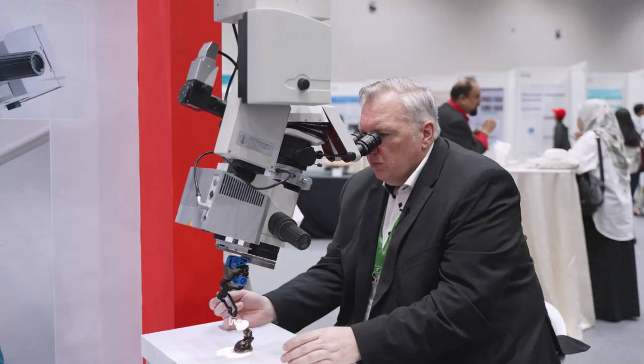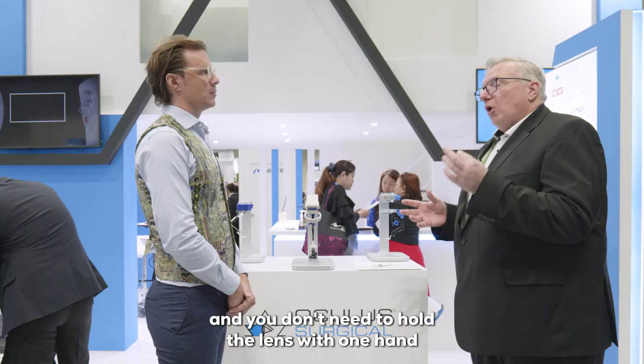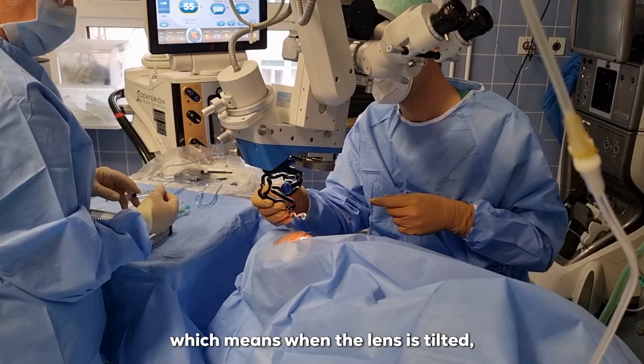It's a safety concern. When you need physical control, having both hands means you can guide your operation hand, move the head, move the eye — without needing to hold the lens with one hand while doing the surgery with the other. Lens position is a very important part during surgery; when the lens is tilted, you lose the view of the chamber angle and cannot see where you want to place your devices.